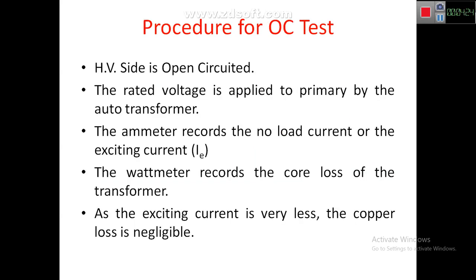Now let us move on to the procedure for the OC test. The HV side is open circuited and the rated voltage is applied to the primary via the auto transformer. The ammeter records the no-load current, which is the exciting current IE. The wattmeter records the core loss of the transformer. Since the exciting current is very small, copper loss is neglected.